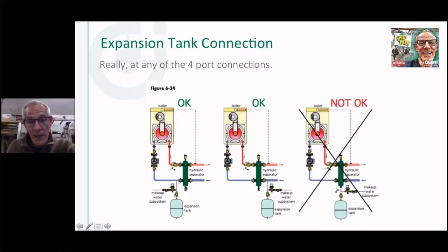I prefer one of these bottom two because, number one, it puts my expansion tank in a little bit cooler fluid. If I'm going out here at 180 degrees, obviously my tank up here would see 180 degrees on the diaphragm or the bladder, or the bag, whatever type of tank you're using. By putting it down on the bottom here, on one of the return sides here, I'm going to see a little bit lower temperature. Not a huge deal, but it might extend the life of that a little bit.